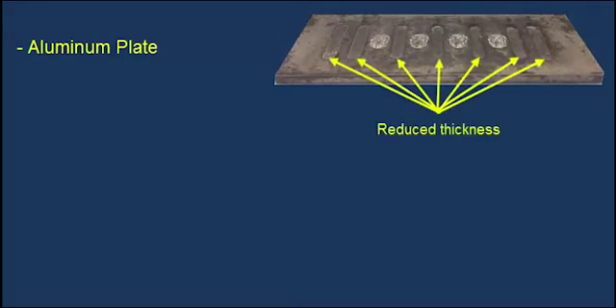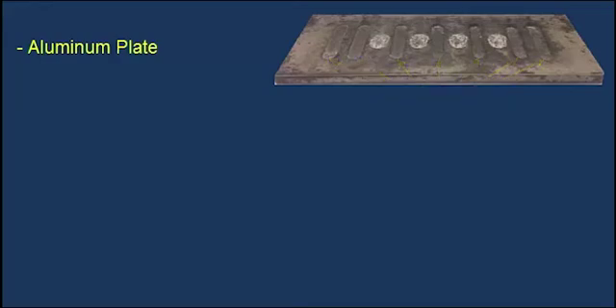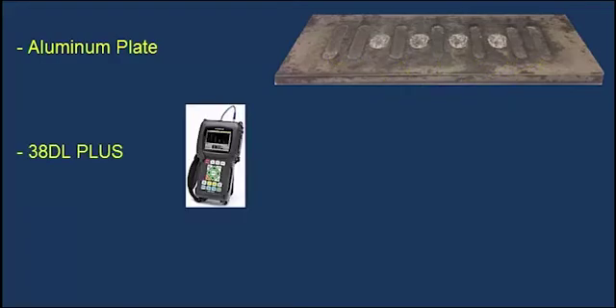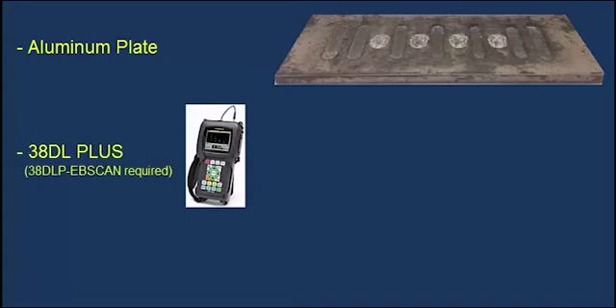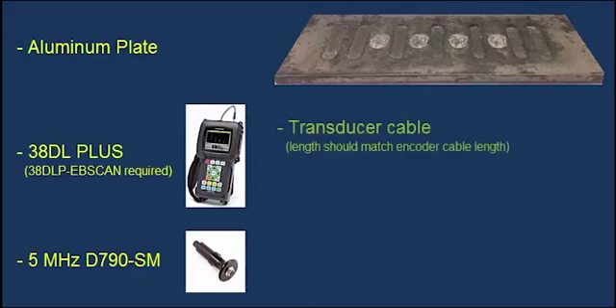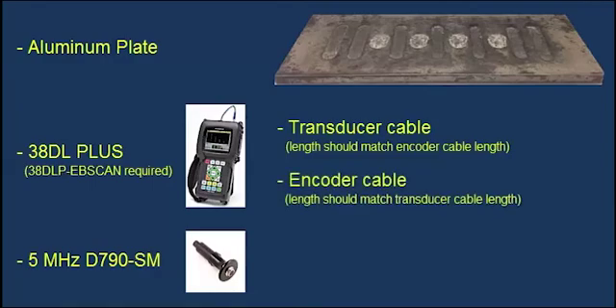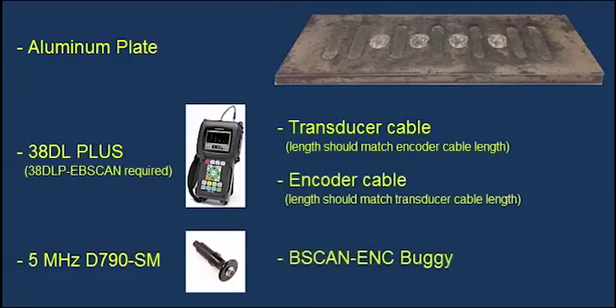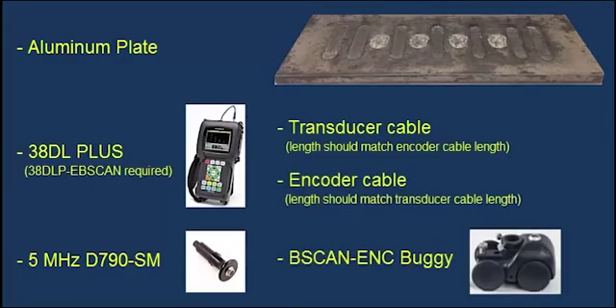We will use the Olympus 38DL Plus thickness gauge with the 38DL Plus encoded B-scan software option activated, along with a 5 MHz D790-SM dual-element transducer, the corresponding transducer cable, an encoder cable, and the B-scan-ENC B-scan buggy.